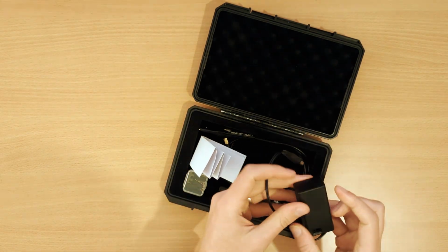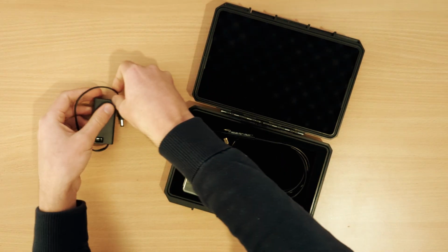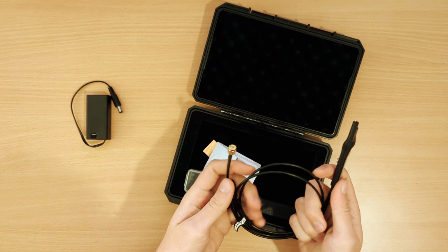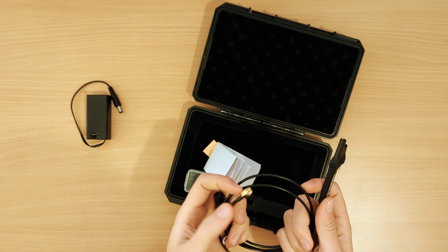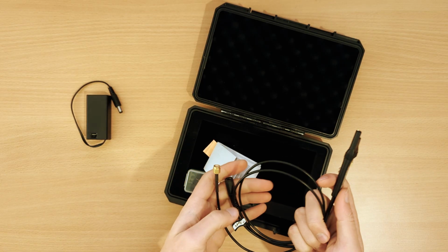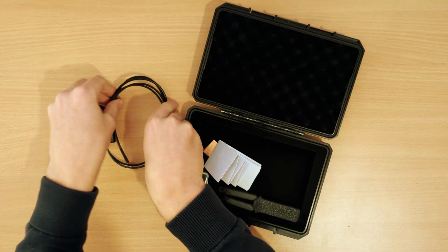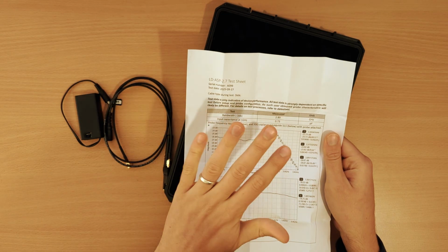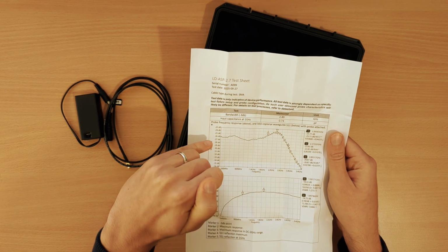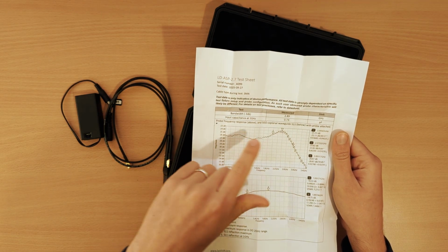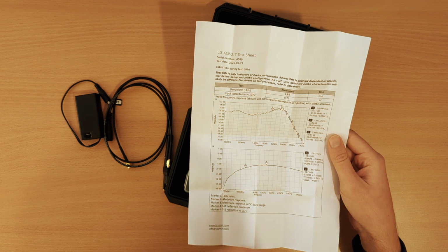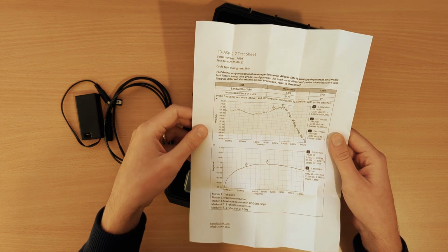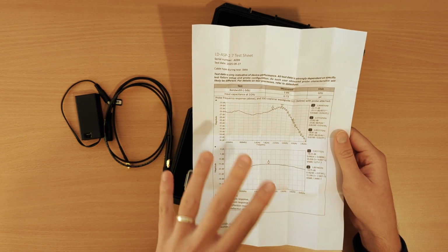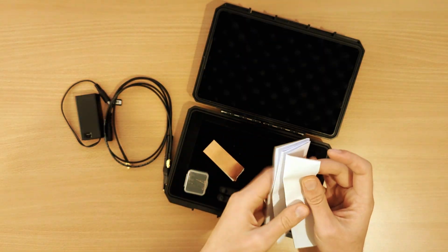So first of all, we have our 9-volt battery box, the probe itself. This guy has an SMA connection, but BNC is available as well. We measure three things on every probe: the bandwidth and the frequency response, the tip capacitance, and finally the return loss with a 50 ohm transmission line with the probe attached. And you get one of these with every probe.